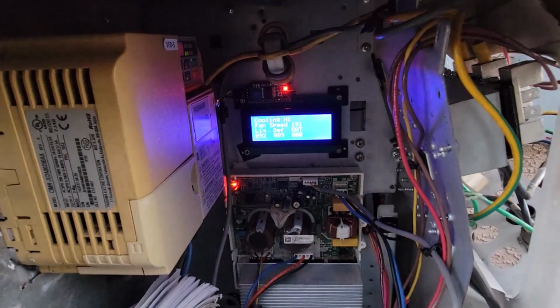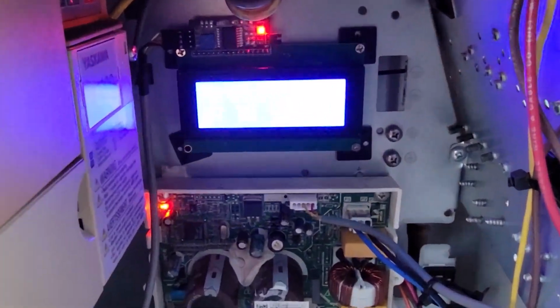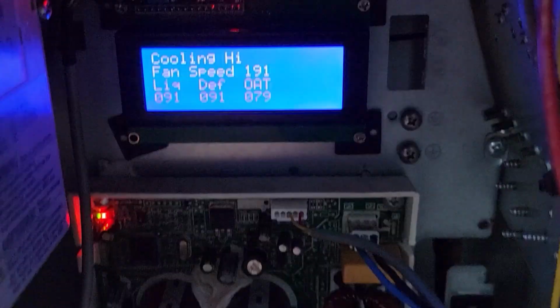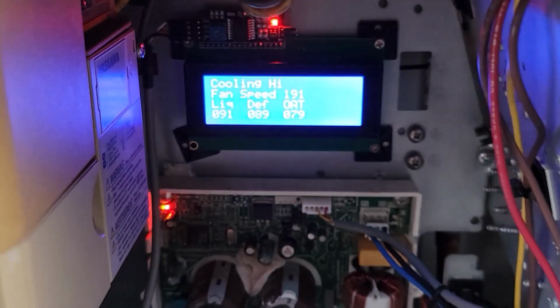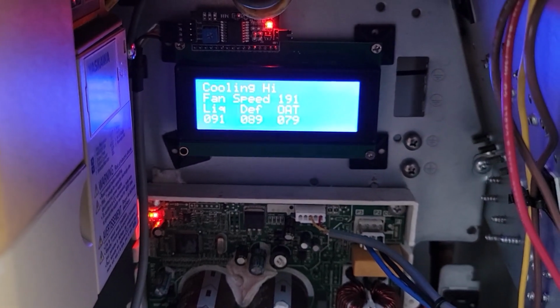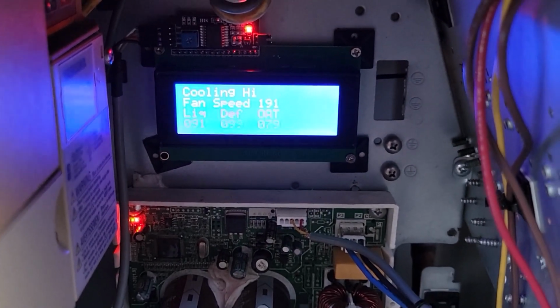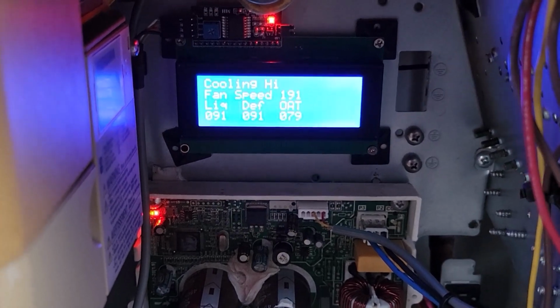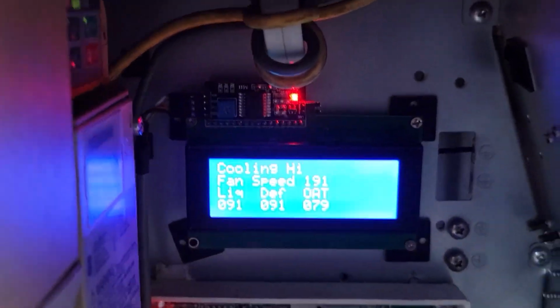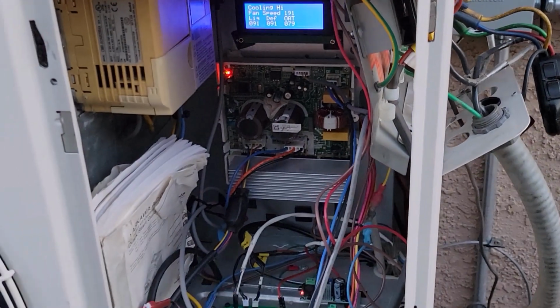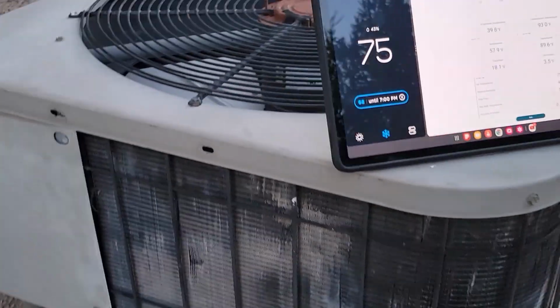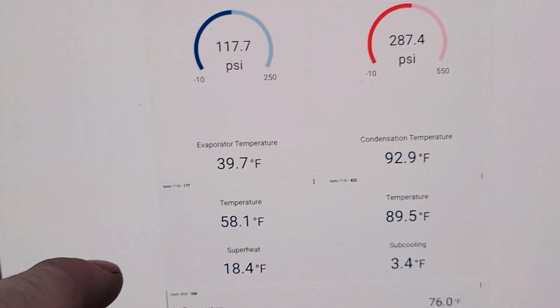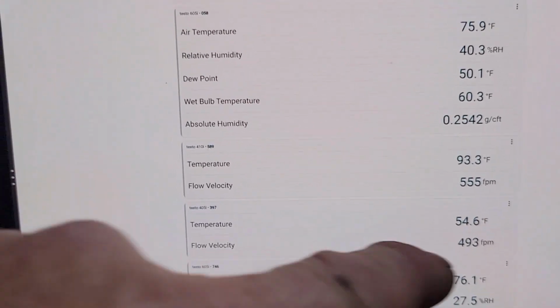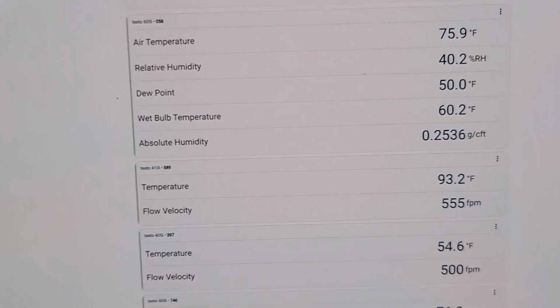And that's the air temperature also; one will lock it out when it's too warm. So I'd probably have to pull this off and put a resistor on there to even test my defrost. So it's too warm for that. I think I have to cut off at 50, 55, something like that. It's not warm, obviously it's not going to be freezing up. So I'm guessing, yeah, look how that's tanking. It's not even near 3 to 1 anymore. It's still cooling good. Yeah, 54.6, 75.9. So basically 76 and almost 55.